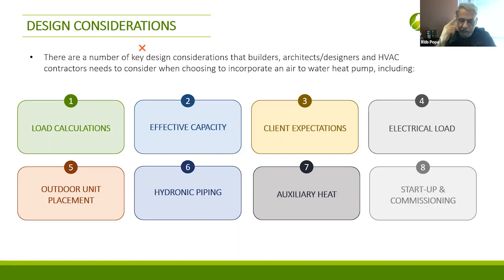Electrical, especially in retrofits, is a big issue - whether or not you have enough capacity on the panel to take on a heat pump. If you had a gas boiler, that would have been a 15 amp circuit. If you change that to a heat pump, now you're at minimum 30, 40, maybe 60 amps. It's a big difference, especially if you have electric backup heat. The point is that the electrical capacity of the house, both in new construction but especially in retrofits, may be a limitation that has to be figured out.